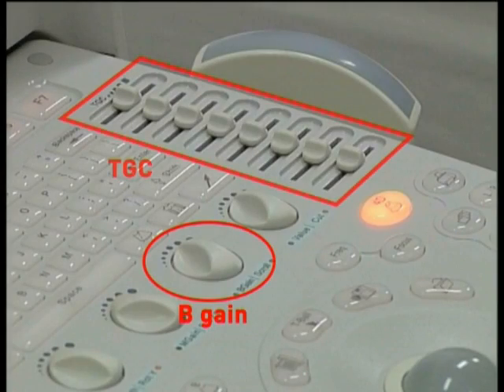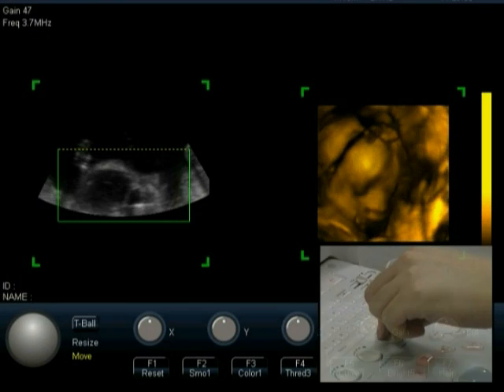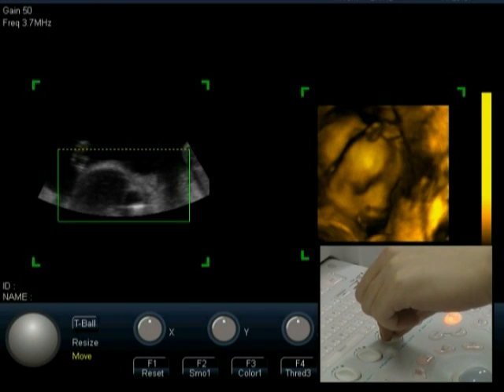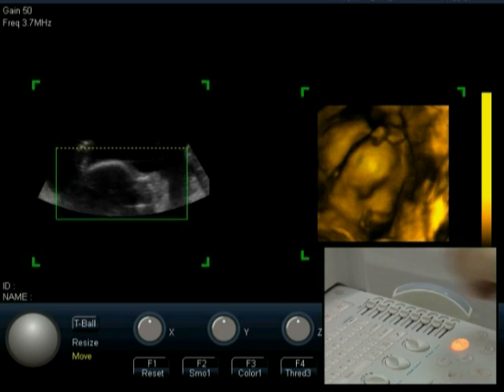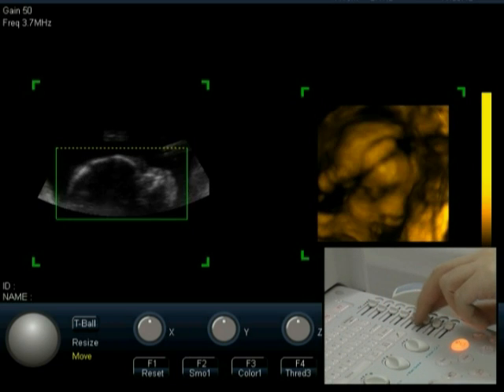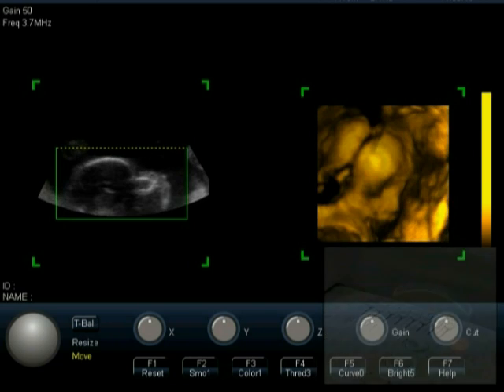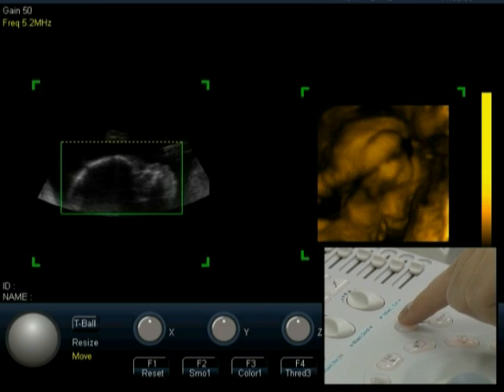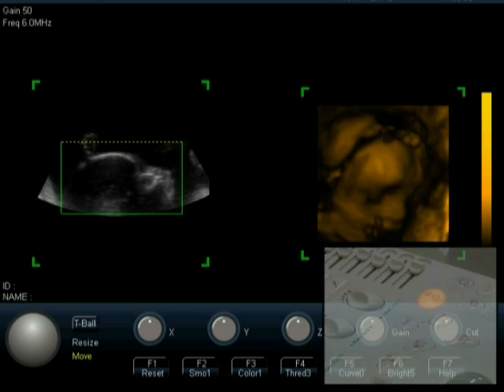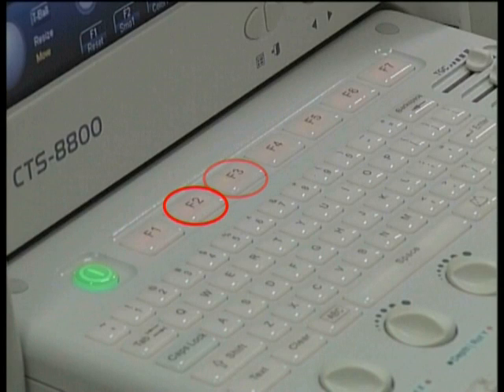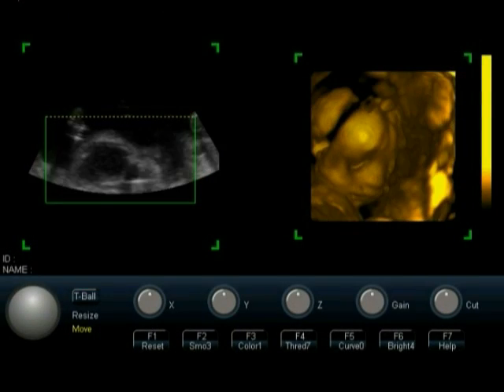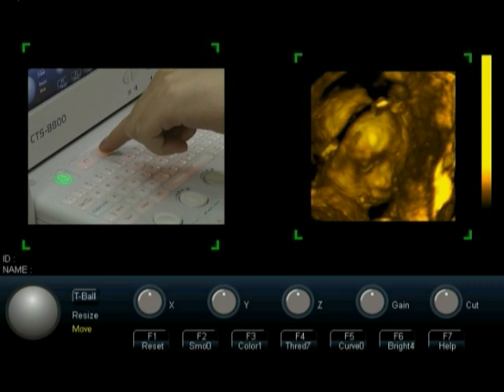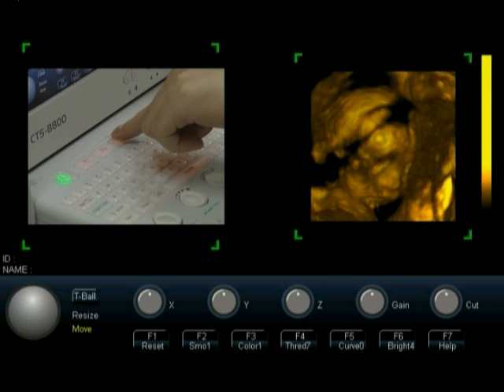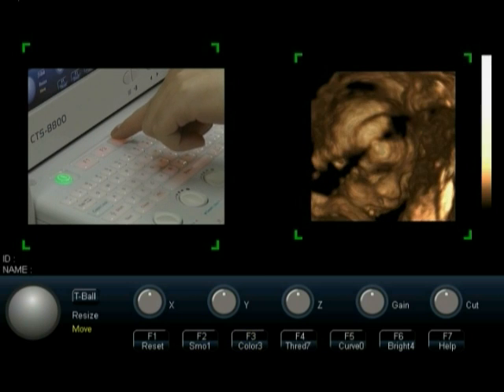In 4D screen, when the image is active, you may adjust the scan parameters of Gain, TGC, and frequency. In 4D screen, use the F2, F3, F4, F5 and F6 buttons to adjust smooth, color, threshold, curve, and bright. The 5 parameters will exert an effect on the 4D image.